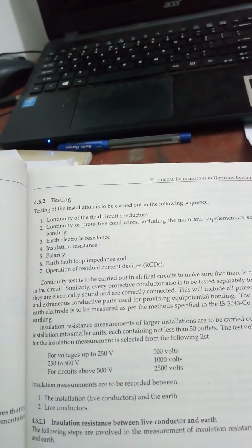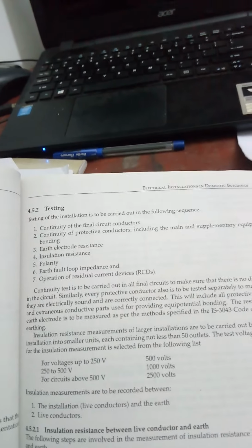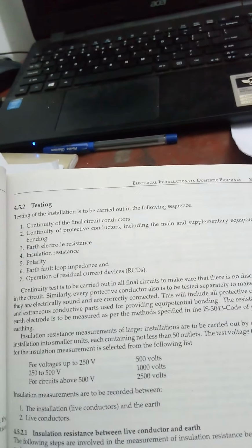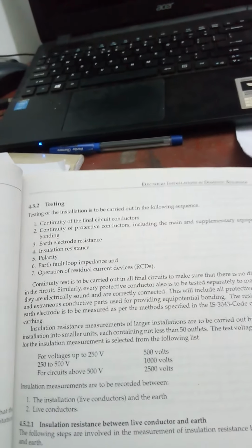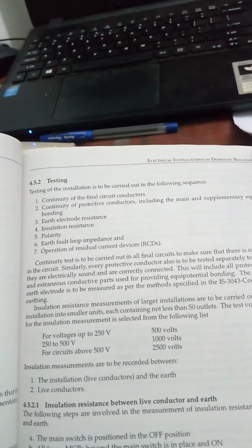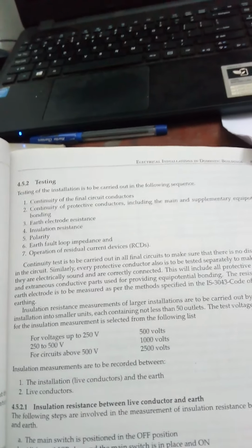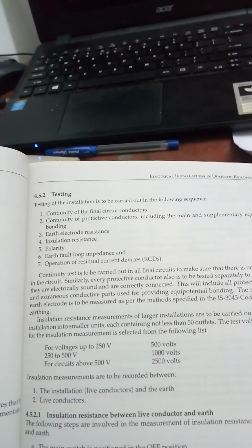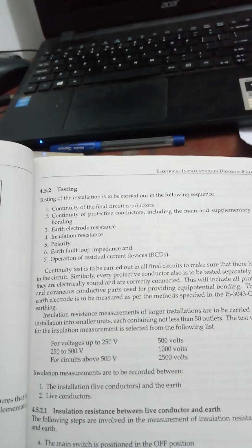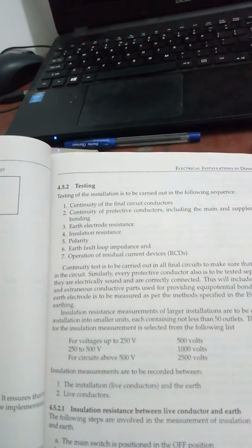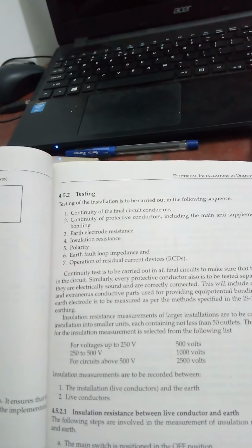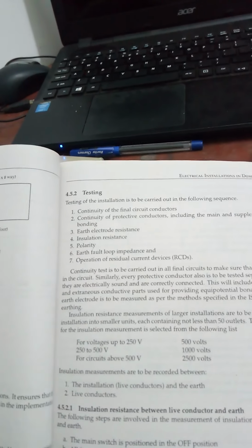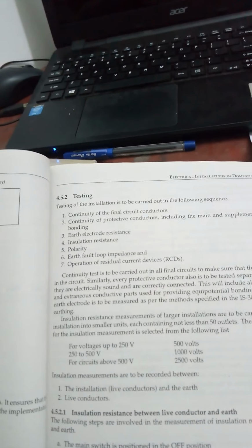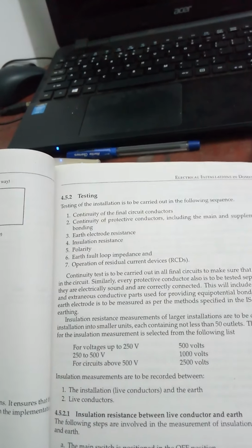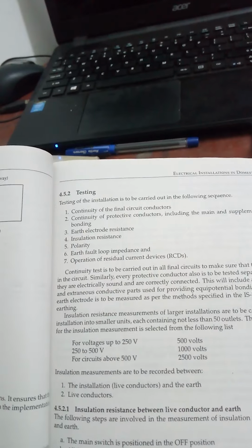The resistance of the earth electrode is also measured and it has to be as per IS 3043 Code of Practice for Earthing. Insulation resistance of large installations is to be measured by dividing the installation into smaller units, each containing not less than 50 outlets. The test voltage is to be applied for insulation measurement. For voltage up to 250 volt, the applied voltage is 500 volt. For 250 to 500 volt, applied voltage is 1000 volt. For above 500 volt, applied voltage is 2500 volt.